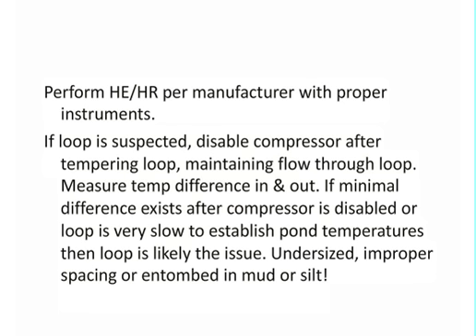Well, I can tell you from what I've seen, because I've dove down on a lot of old systems. Mud and silt, very, very common. If it was a plate heat exchanger, perhaps it fell over, or in one case I had a customer who didn't like the chain that he saw underneath his dock suspending his GeoPlate heat exchanger. He disconnected it and laid it down against my recommendations. And when he called and told me he was having performance issues, I made sure that I asked him a lot of questions, finally got him to admit that he laid it down. So I told him he's got to go get cold in the water and pick it back up and hang it vertically. So typically that's what I've seen on some projects.